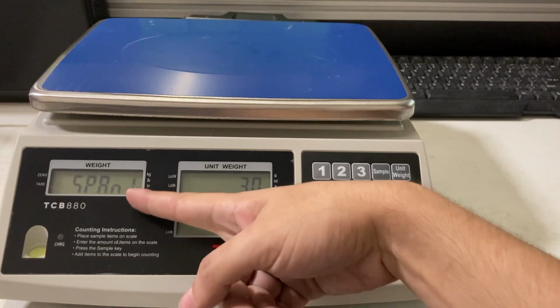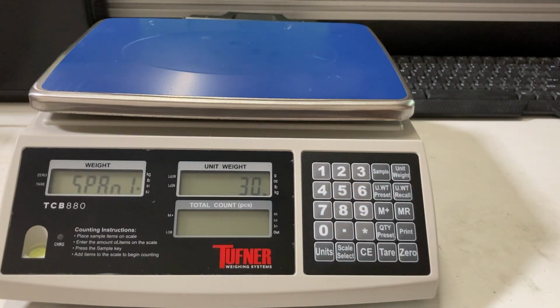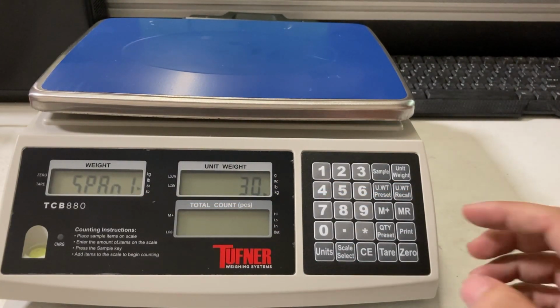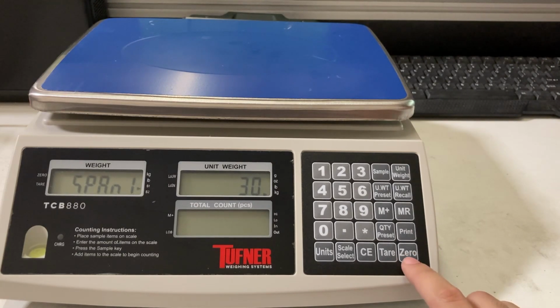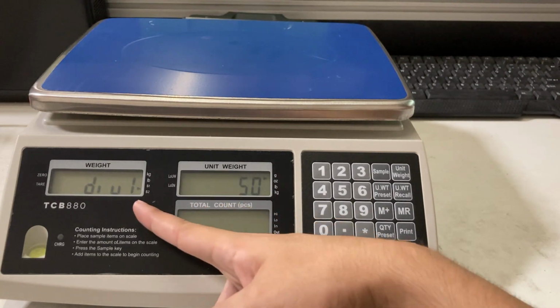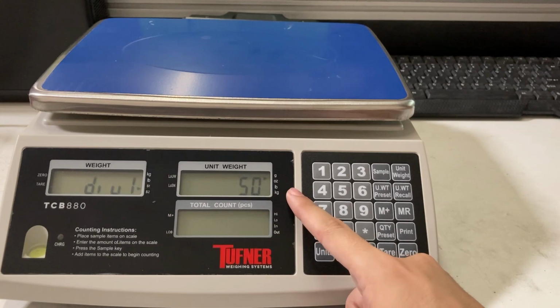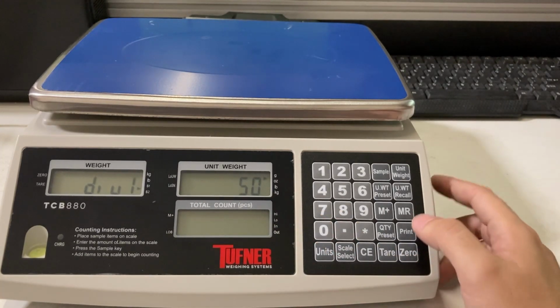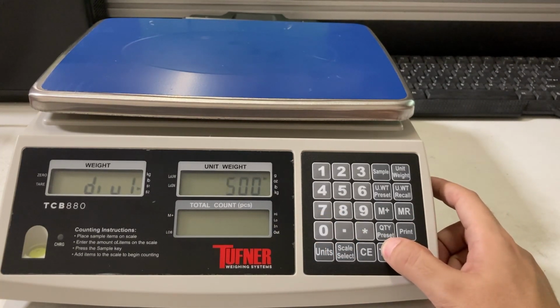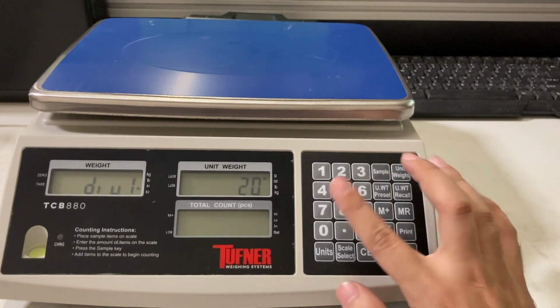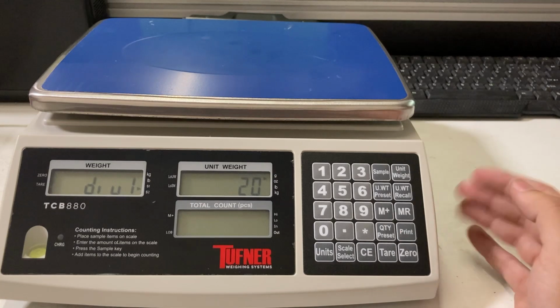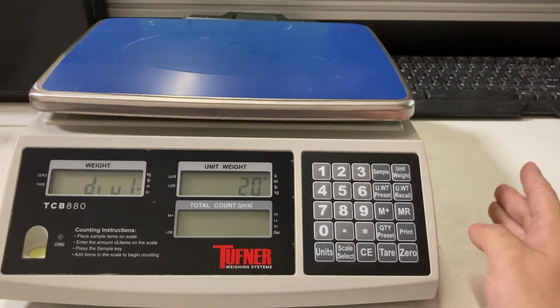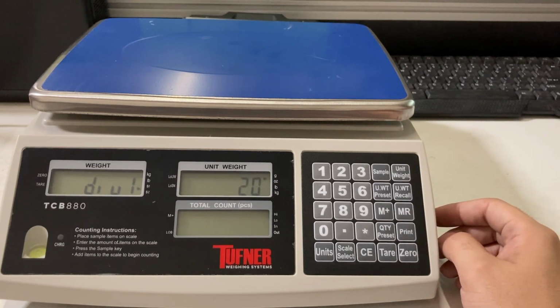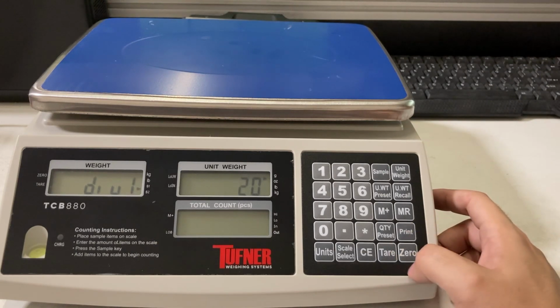This is all done in kilograms, so you have to get the kilogram equivalent of whatever you're calibrating it to. After you change span 1, just the capacity, press the 0 button and you'll see DIU1 and 50 - that's the amount of divisions. I currently have it set to 50, but I can set that to 10, or I'll set it to 20 for now. That's the amount of divisions you want - I want 20 grams of accuracy within 30 kg, which is fine for my application.